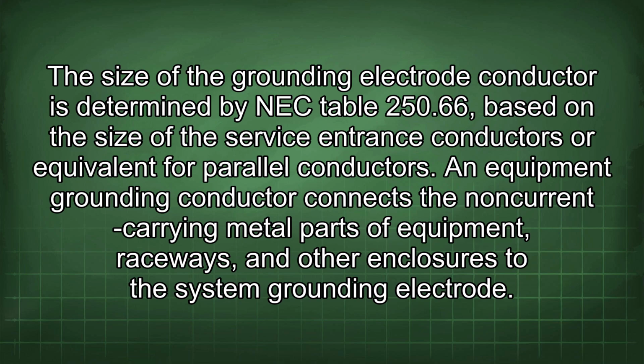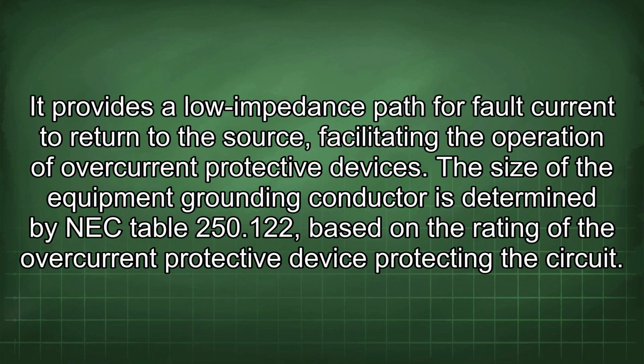An equipment grounding conductor connects the non-current carrying metal parts of equipment, raceways, and other enclosures to the system grounding electrode. It provides a low impedance path for fault current to return to the source, facilitating the operation of overcurrent protective devices. The size of the equipment grounding conductor is determined by NEC Table 250.122, based on the rating of the overcurrent protective device protecting the circuit.